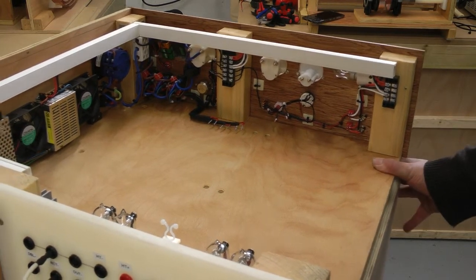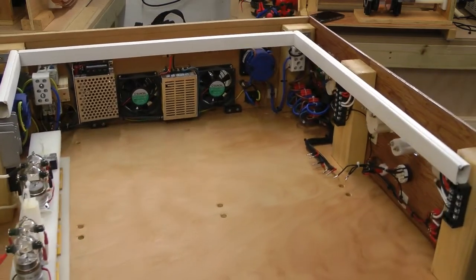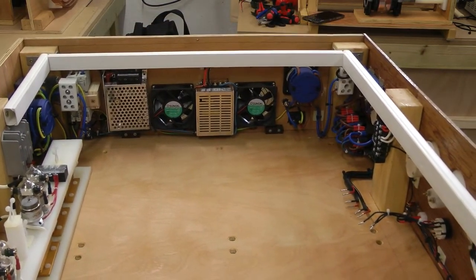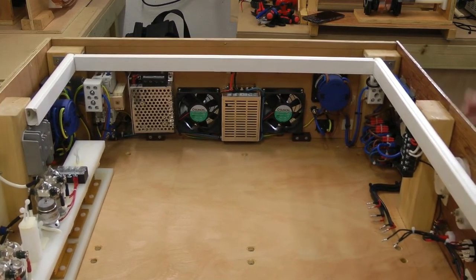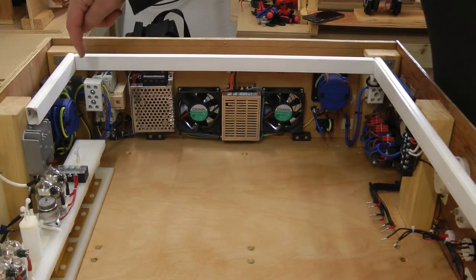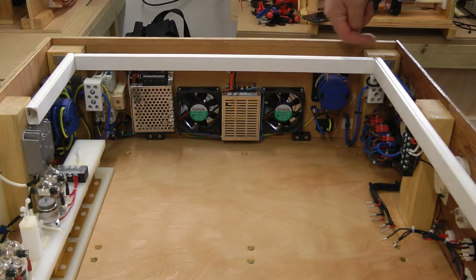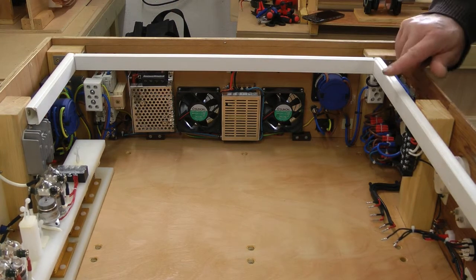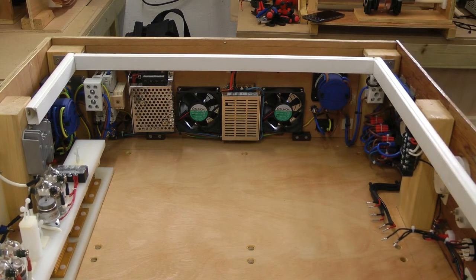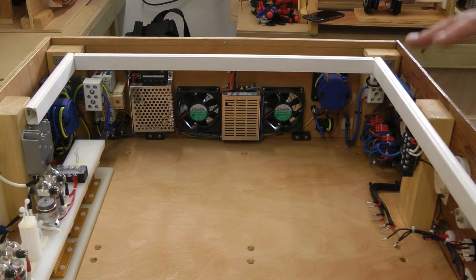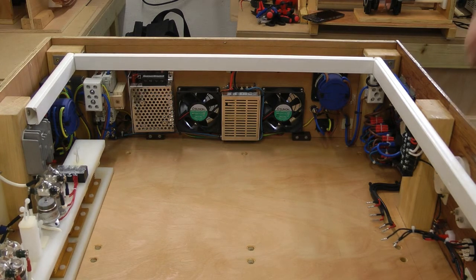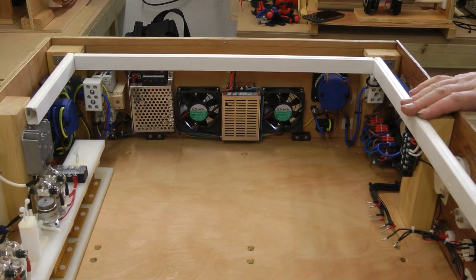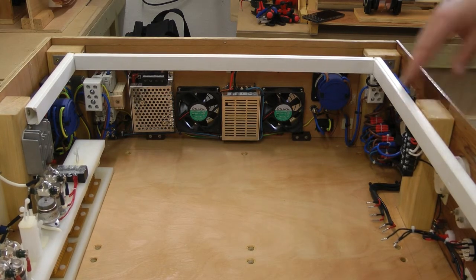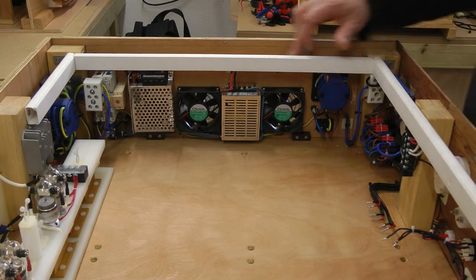Power comes in, let me just put it at the back. The design is arranged to be simple, so power comes in at this side and progresses down this way into the front panel and then into the transformer module. That makes the wiring more simple and also leads to a natural, logical way in which the thing is designed and assembled, which also makes it easier to repair and work on should there be a problem. Wiring that has to be passed, interconnecting wiring, is in this conduit here.